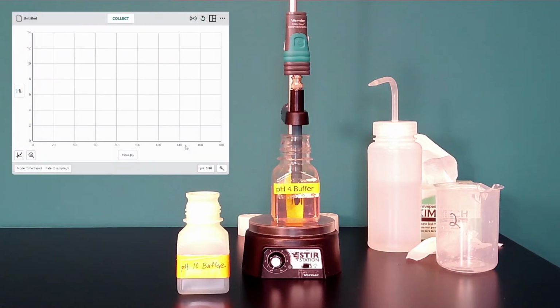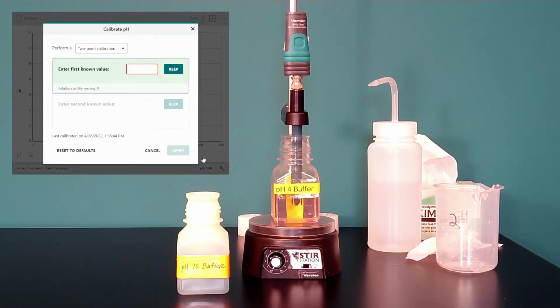I want to make sure the pH channel is enabled, and then I click Done. To calibrate, from the Sensor Actions bar, I select Calibrate. Now my pH sensor is already in my pH 4 buffer, so the relative stability reading is stable. And now I'm going to type in the pH 4 value and select Keep.